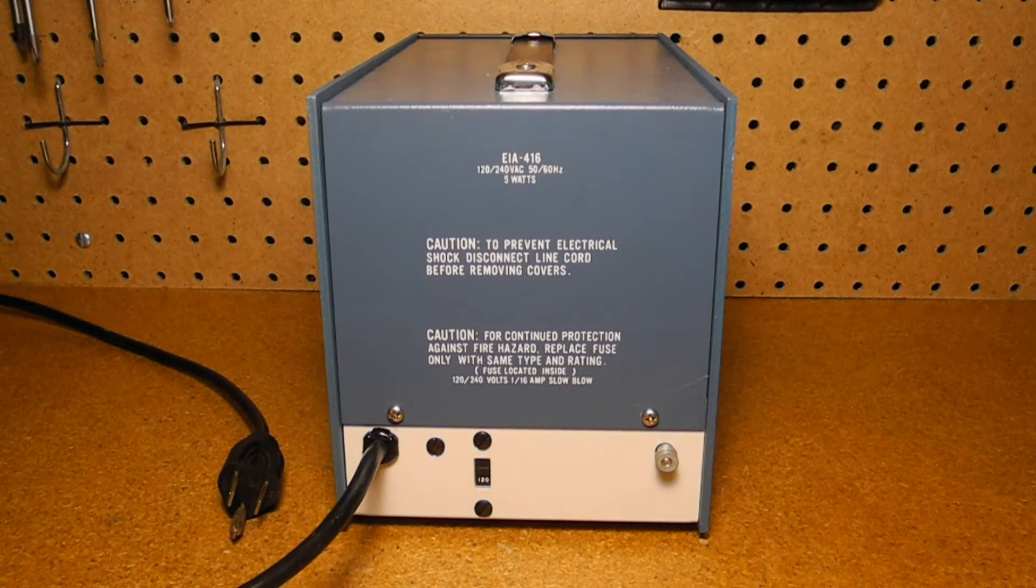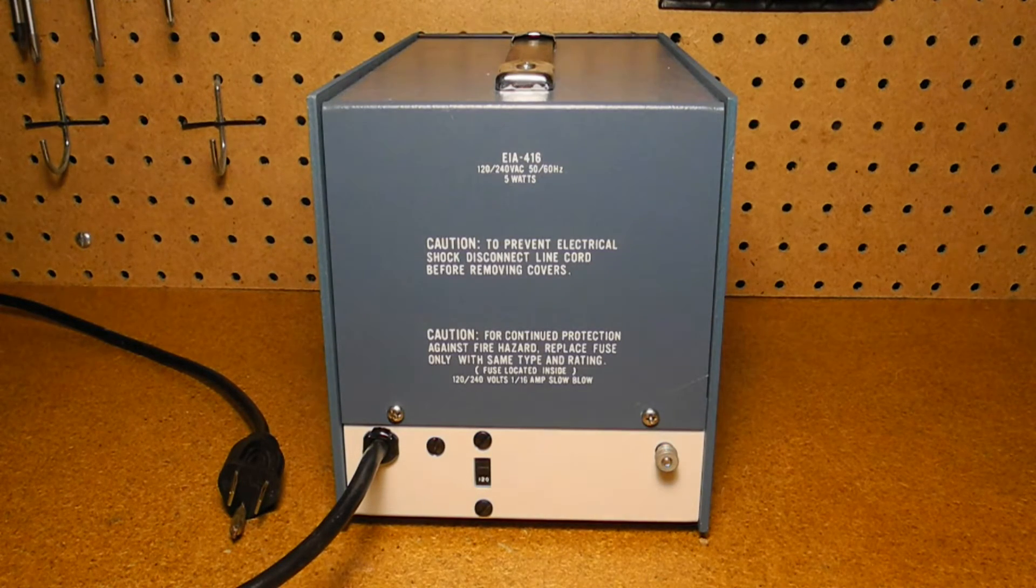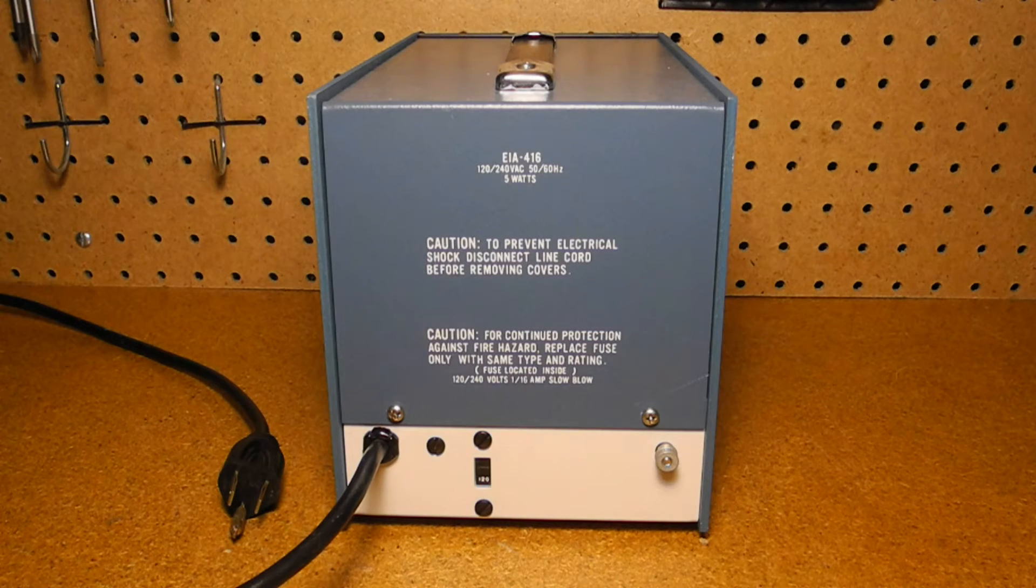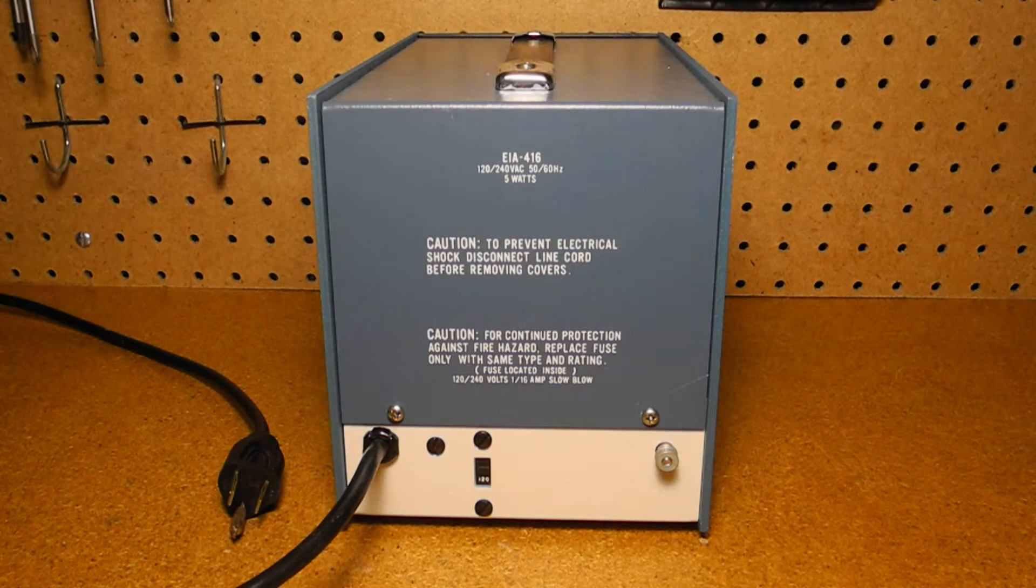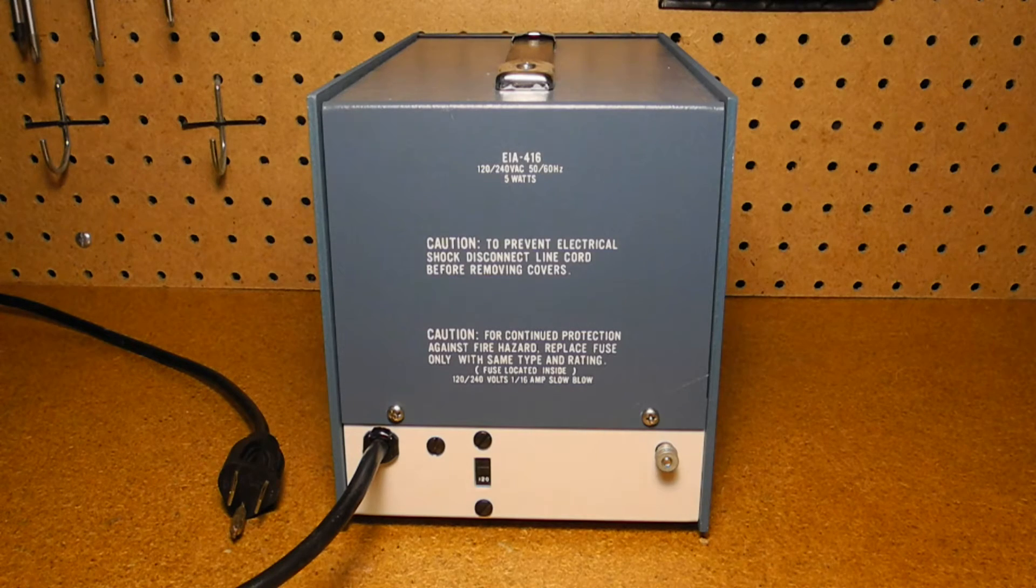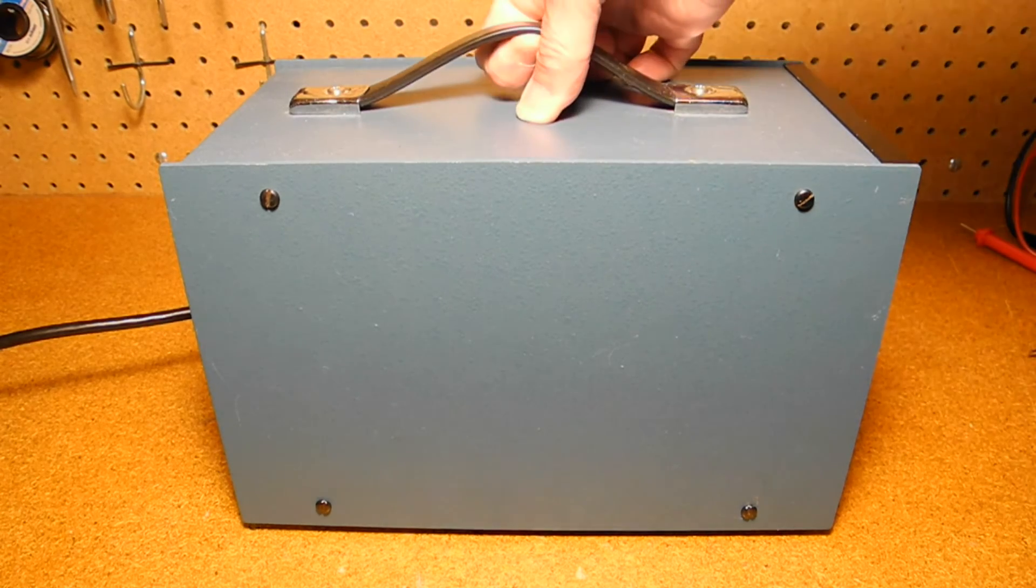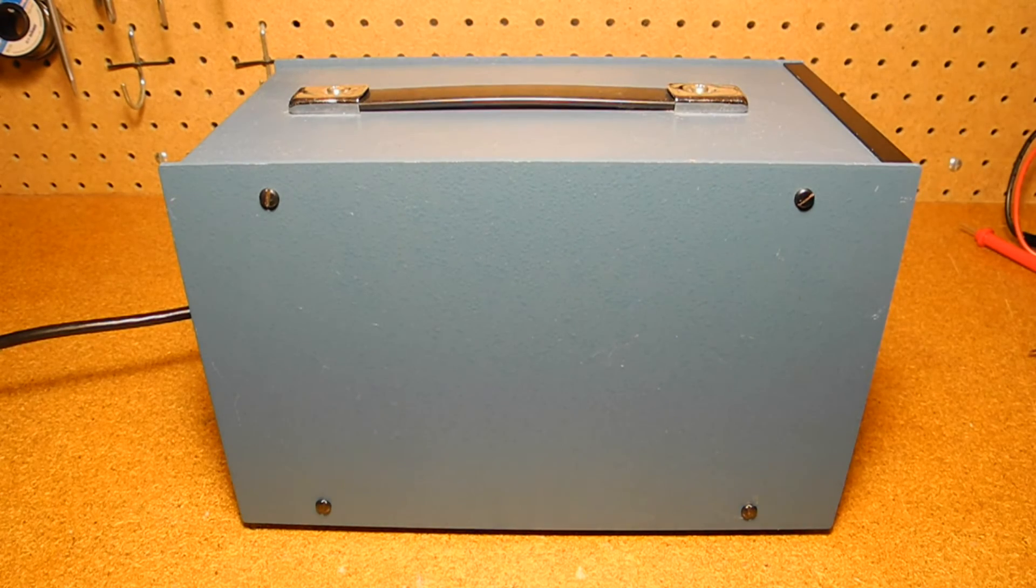On the rear panel is a wired power cord, the 120/240 volts AC power selection switch, and a terminal connected to the AC ground. The meter inputs are floating, so you can connect to ground here to reference it to AC ground. The unit has a carrying handle on top, and the standard Heathkit stick-on rubber feet are on the bottom.